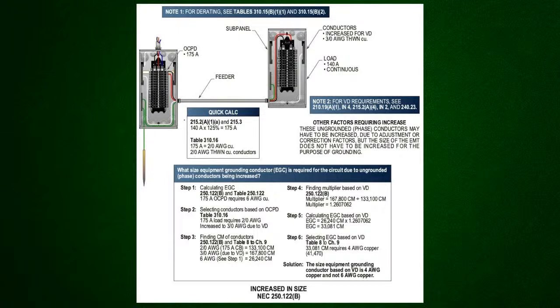So what we did, we just made up a problem for you. We're going to go over to this other panelboard, and it has 140 amps of continuous load. Now, if I go look at 215.2(A)(1)(a) and 215.3 for the overcurrent protection device, you would take 140 amps at 125%. That gives you 175 amps. If you go to table 310.16, the size that matches up is a 2/0 conductor. Now, let's say that I have to increase this due to voltage drop, or it could be adjustment factors, correction factors, whatever. We have to increase the size of this conductor, and we'll just say we already did the calculation, and we had to increase the size up to a 3/0 conductor.